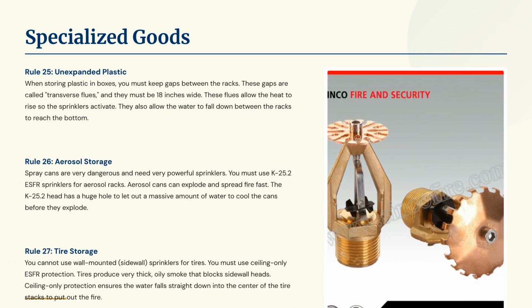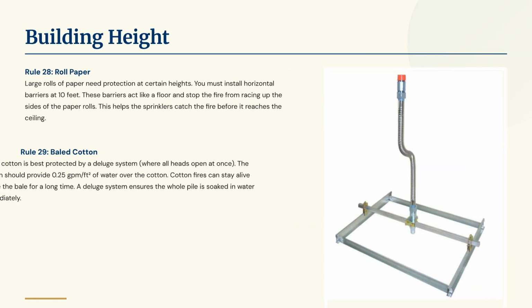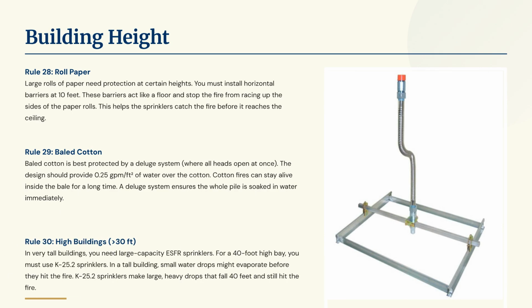Rule 25 requires 18-inch transverse flue spaces for unexpanded plastic storage. Rule 26 mandates K25.2 ESFR sprinklers for aerosol storage due to the risk of explosions. Rule 27 prohibits sidewall sprinklers for tires, requiring ceiling-only ESFR protection. Rule 28 requires horizontal barriers at 10 feet for large paper rolls.